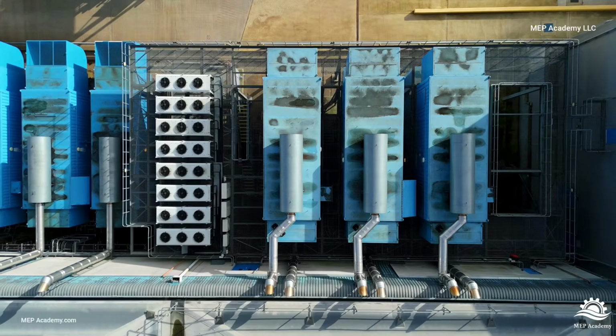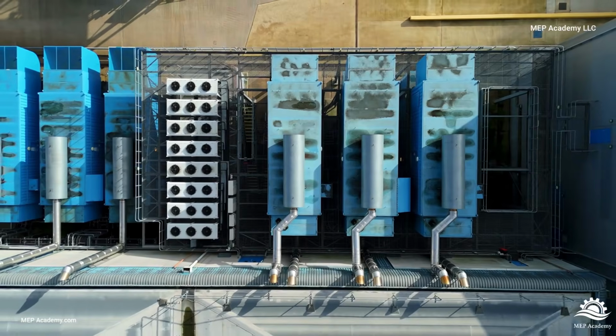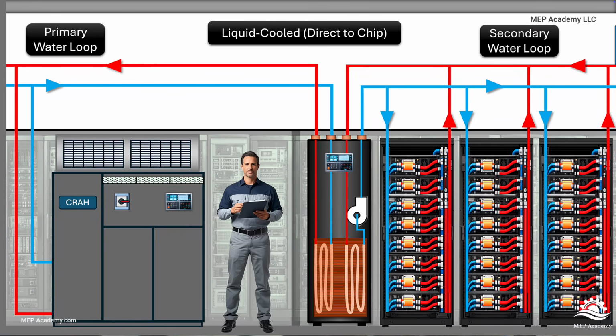One question many people ask is, how does the water actually get to the server rack? Most modern liquid-cooled data centers include a cooling distribution unit, often called a CDU. Think of the CDU as the interface between the building cooling system and the IT equipment. The CDU circulates coolant through the racks while maintaining proper temperature, pressure, and flow rates.